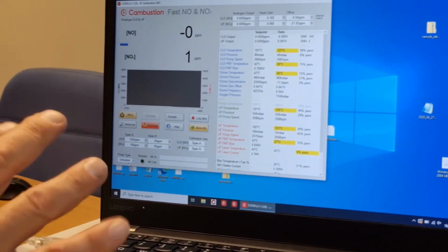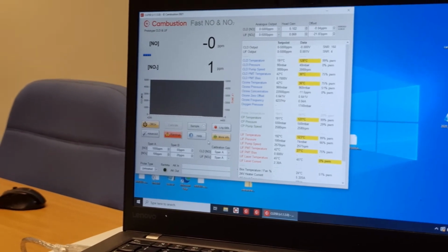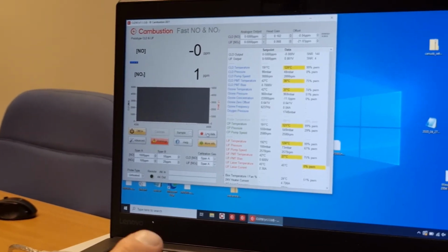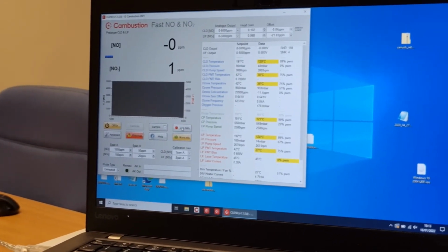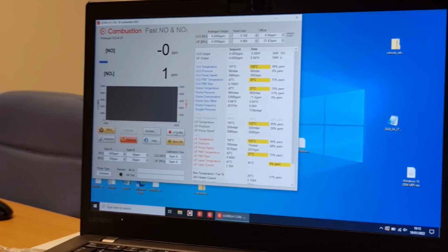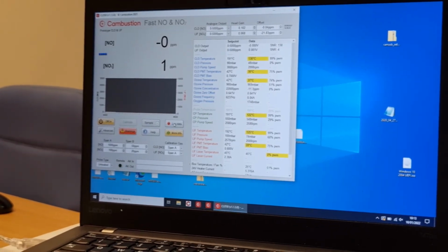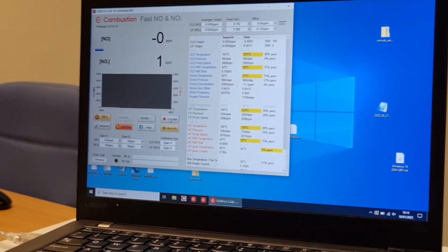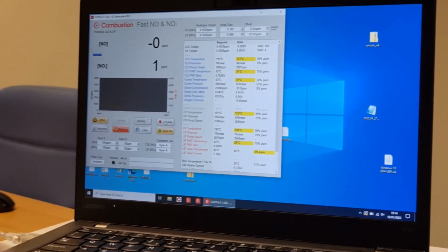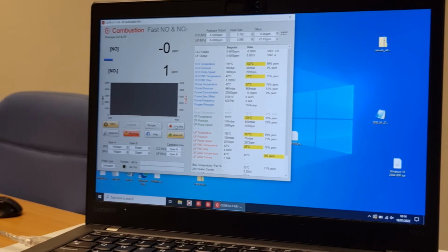If you want to log data simply from the user interface, there is a logger which operates at about 10 Hz, and if you press that button, it will log data to a file with a timestamp. It's just a CSV file, but a timestamp alongside the NO and the NO2 concentrations.